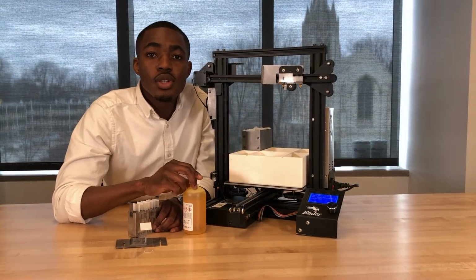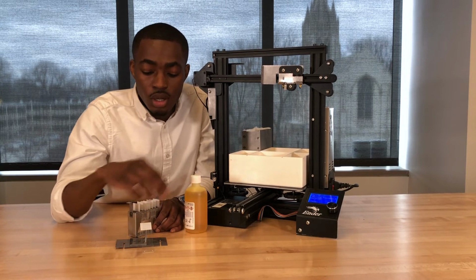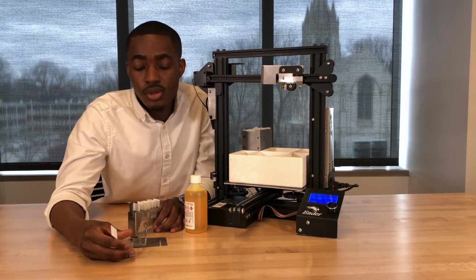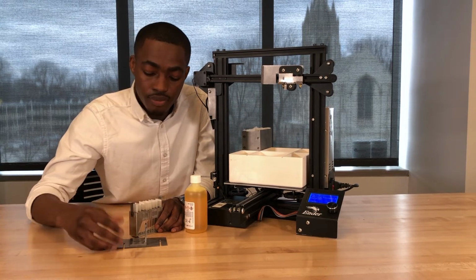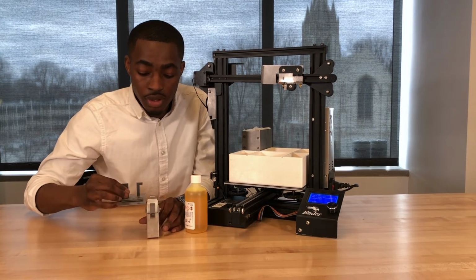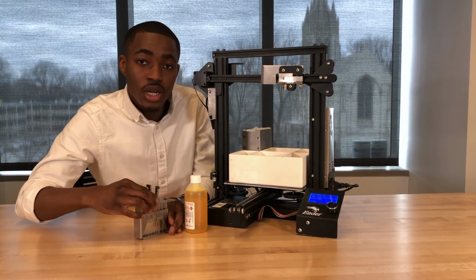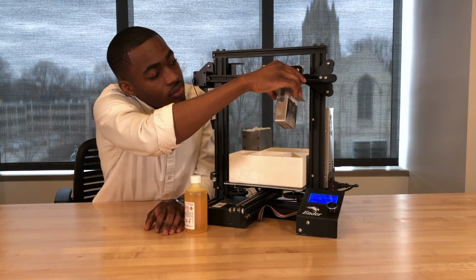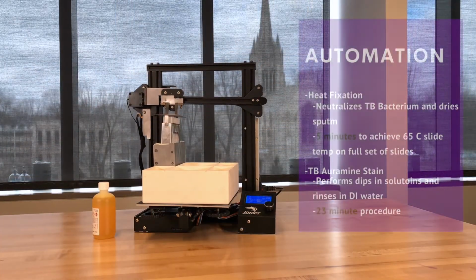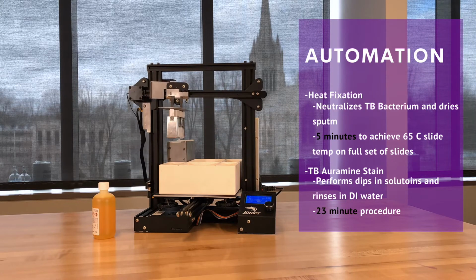POCAS is pretty simple to use with the TB auramine stain. Once the technician has made fresh sputum samples, they insert them into the slide rack, assemble the slide carrier, dock it onto POCAS, and press start. The most astounding aspect of POCAS is that at its core it is a standard 3D printer.